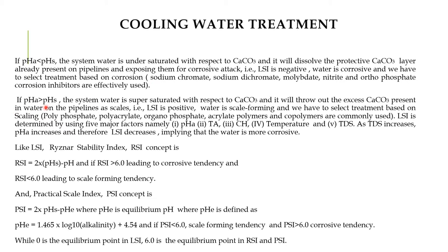If pH actual is greater than pH saturated, the water is supersaturated with respect to calcium carbonate and will throw out excess calcium carbonate, depositing scales on pipelines. A positive LSI means water is scale-forming, and treatment should be selected based on scaling control. Polyphosphate, polyacrylate, organo-phosphate, acrylate polymers, and copolymers are commonly used.